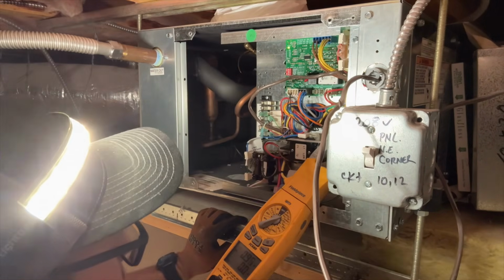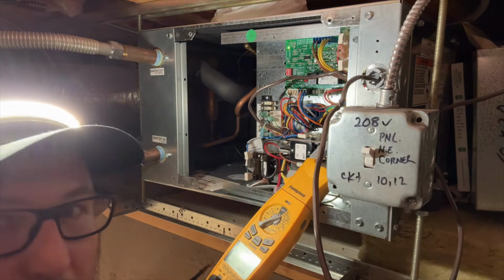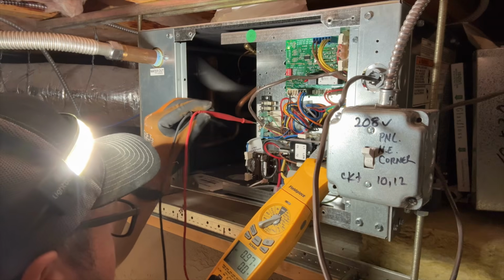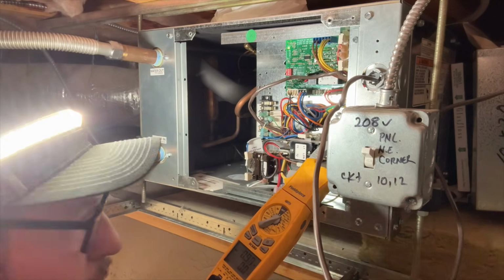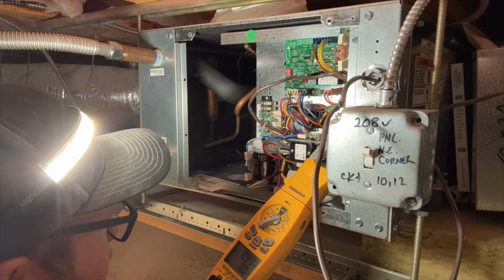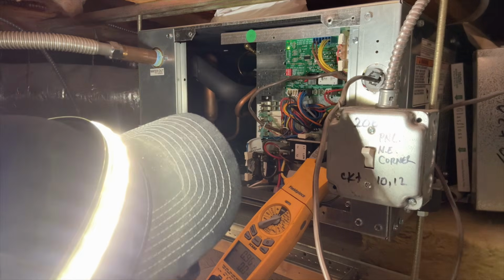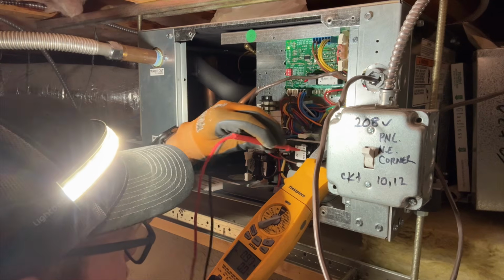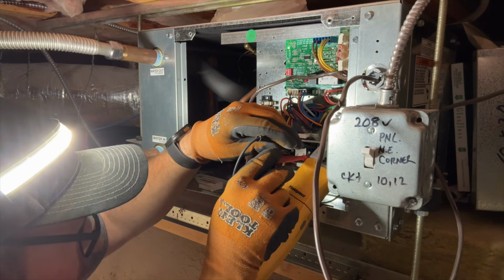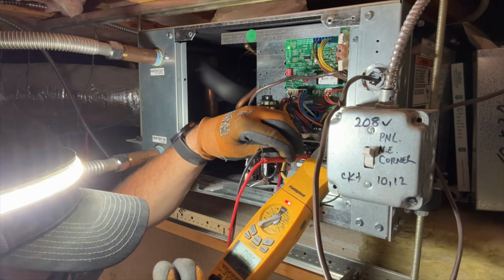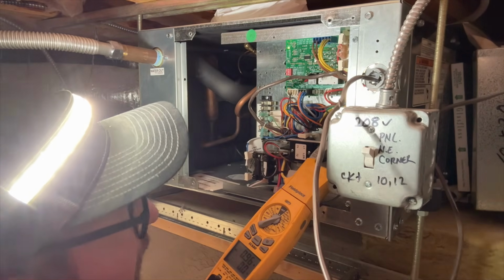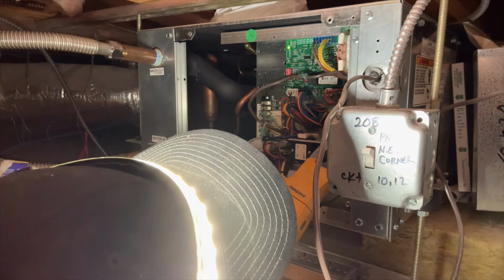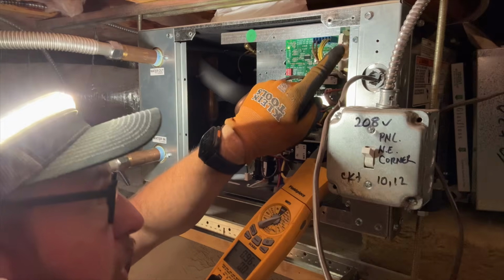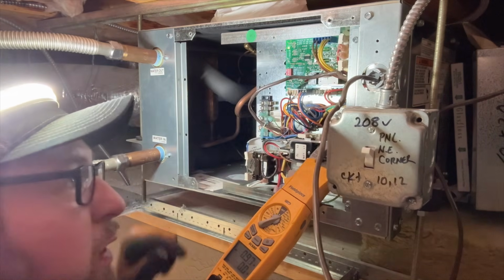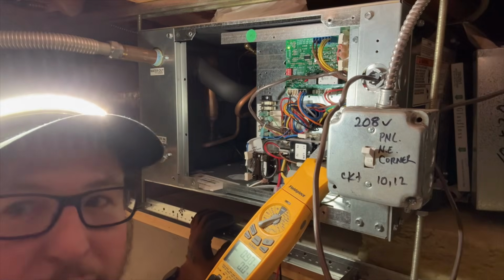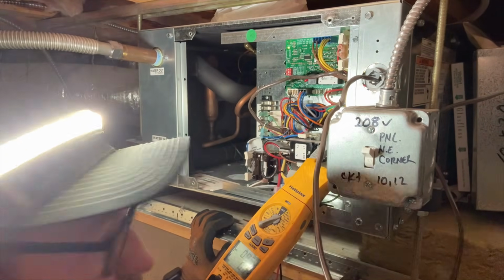All right, so in heating it never got past 5.5 amps, so we are now going to put it in cooling mode. There's a slight time delay. All right, so I'm getting 22 volts on the control side, which is a little alarming. That means that the, what do you call it? The transformer is not set up properly. It's set up for 240 probably. Yeah, because we're definitely at 208, or 230, or 208, and this is currently set to 240. So we got to move this red wire from here to here to get a good 27 volts. But I'll do that after I test this thing in cooling mode.